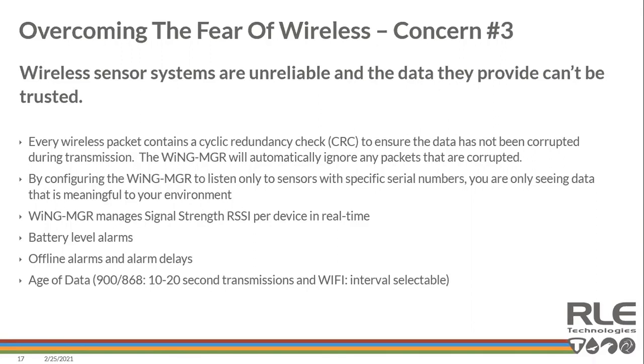On the Wi-Fi side, it's an interval—300 seconds for a 5-minute interval. I generally like to put a 16-minute offline alarm on Wi-Fi, trying to send 3 packets before we trip an alarm, because we want to minimize those. But this is also a good tool to understand how good your Wi-Fi network is.